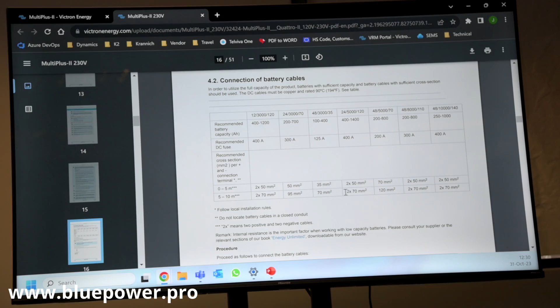Battery cables - there's our cable sizing guide. I always recommend putting in 2 cables. Section 4.2, there we go. So use a torque wrench with an insulated box spanner to avoid shorting, and it's 12 Newton meters for the M8 nut. Most MultiPlus and Quattro inverters all have the M8 nut, so you can torque that up to 12 Newton meters.